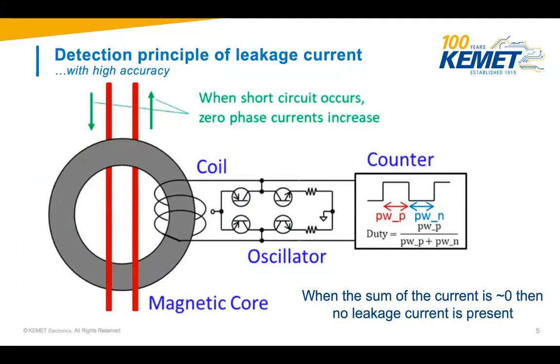The tricky thing is how to detect DC leakages, and there's a bunch of different possibilities to do this. We do it in that way that when there's a DC overlaid in a coil, it will change the duty cycle from the oscillator. Usually when there's no leakage, you have a 50% duty cycle, meaning 50% on, 50% off time. When there is a DC leakage current, the pulse time will change and increase, so it could go up to, for instance, 60% duty cycle, where you have 60% on time and only 40% off time. That's the basic principle.